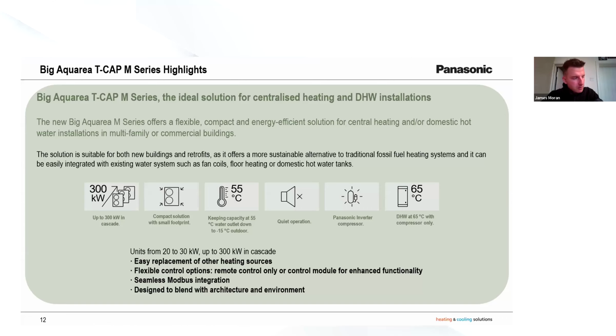But what else has it got? It's got TCAP technology, which stands for total capacity. As you may be aware, some heat pumps, as it gets colder outside, the kilowatt output reduces as it works harder, like a bike or car going uphill. But with TCAP technology, it keeps that kilowatt output all the way down to -15. So if you've got a 20 kilowatt unit, you're getting 20 kilowatts out of it, doing what it says on the tin, which is very key at design stage when considering different climates in the UK, which we get pretty much daily.